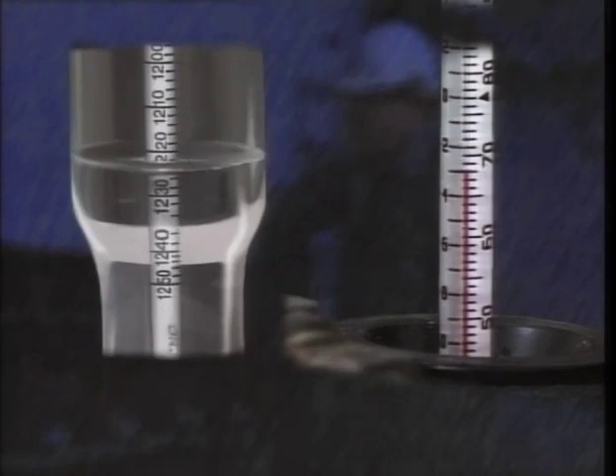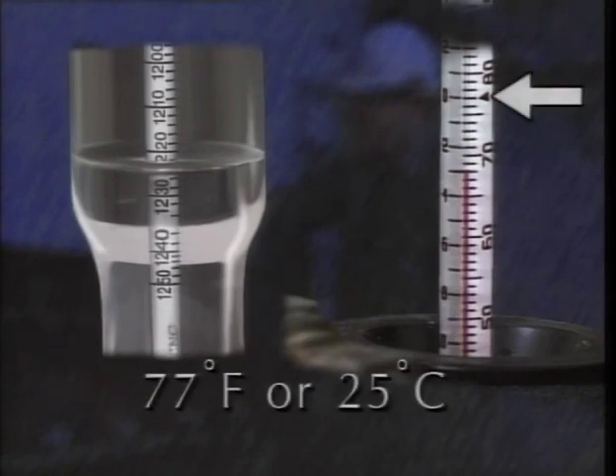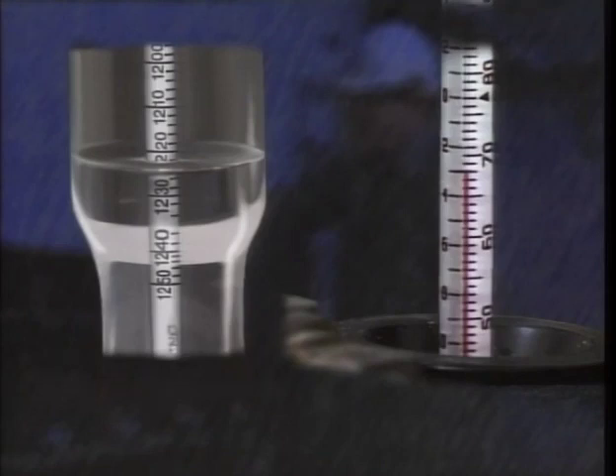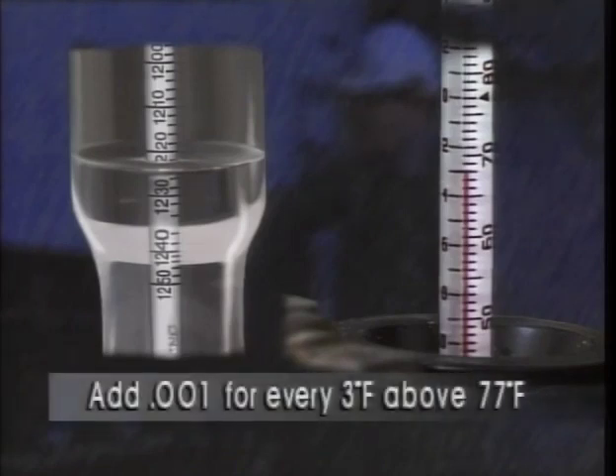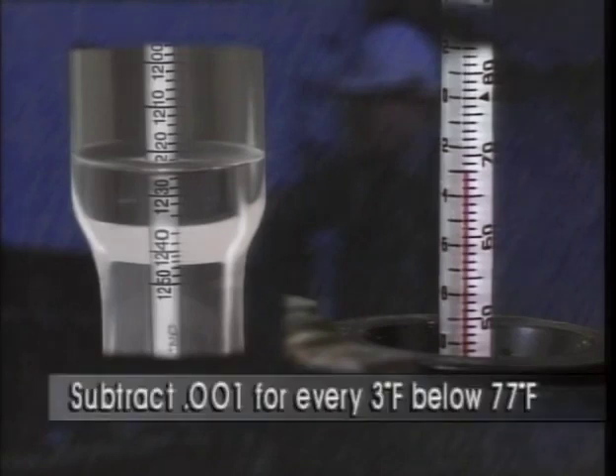The normal or standard reference temperature for electrolyte is 77 degrees Fahrenheit or 25 degrees Celsius. To get an accurate specific gravity reading, the specific gravity is corrected by adding 0.001 to the hydrometer reading for every 3 degrees above 77 degrees Fahrenheit. For every 3 degrees below 77 degrees Fahrenheit, 0.001 is subtracted from the specific gravity reading.